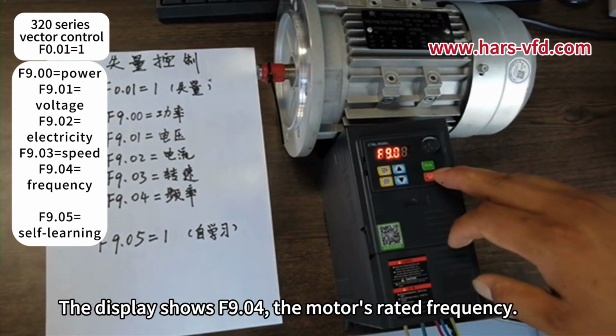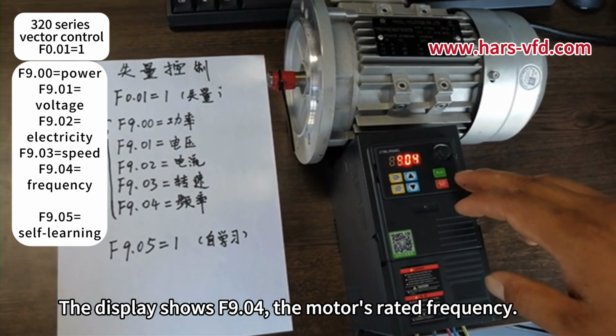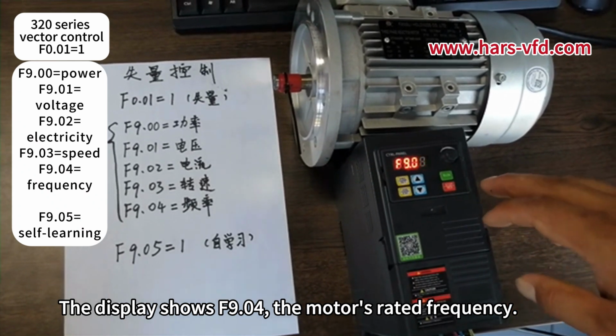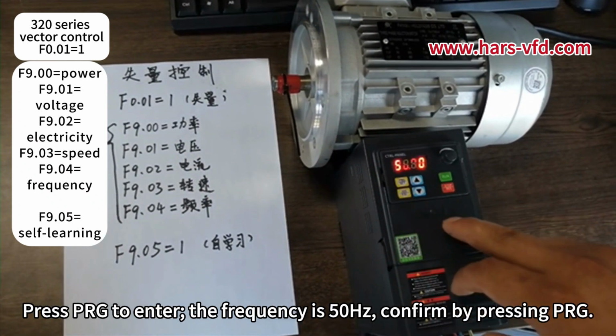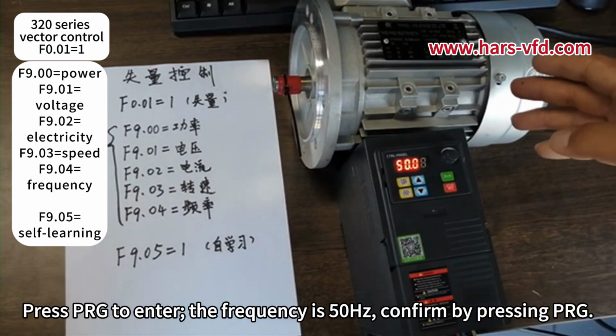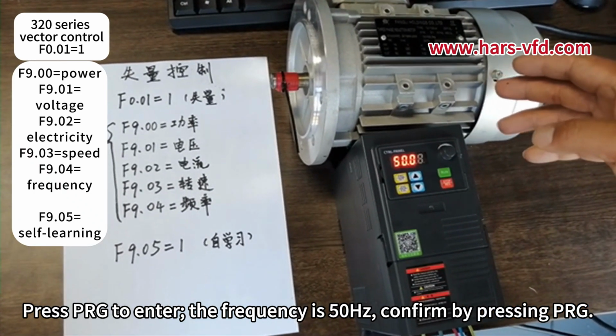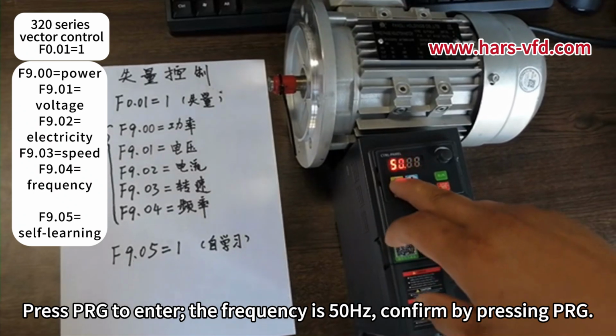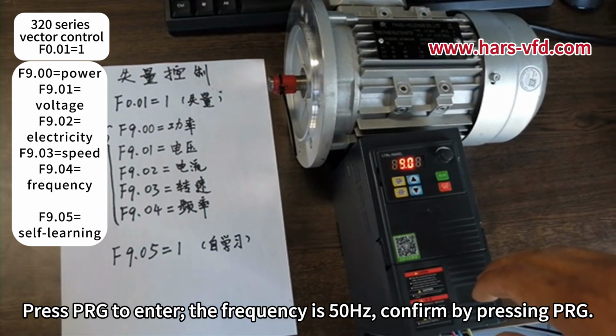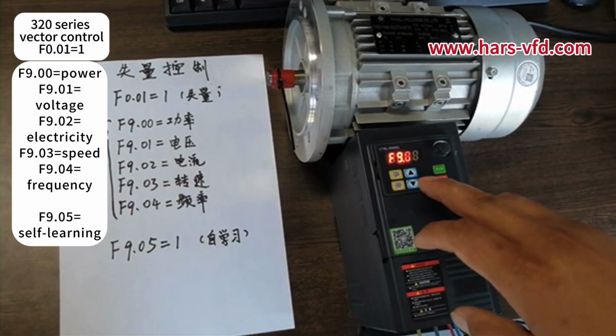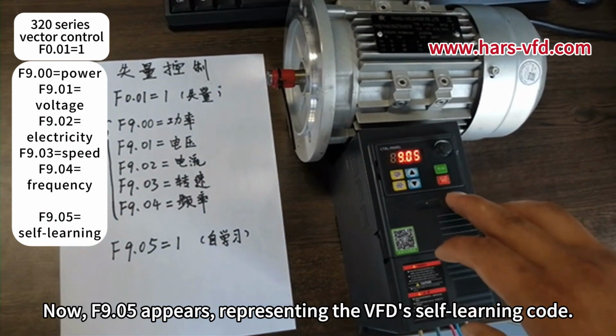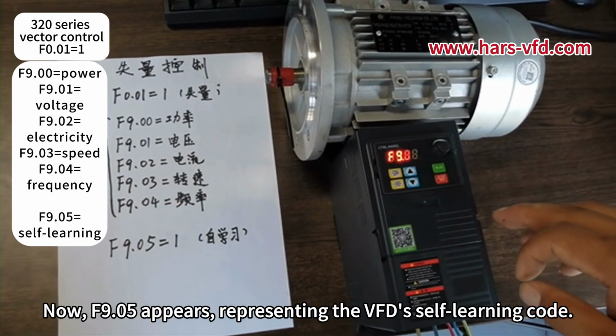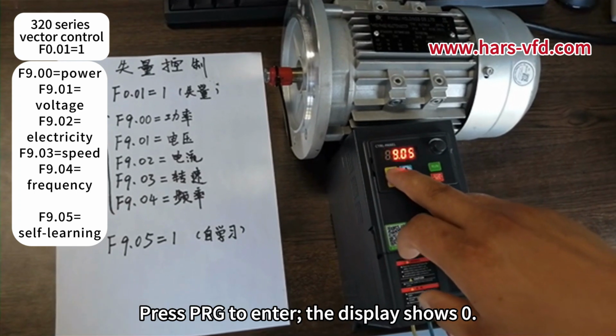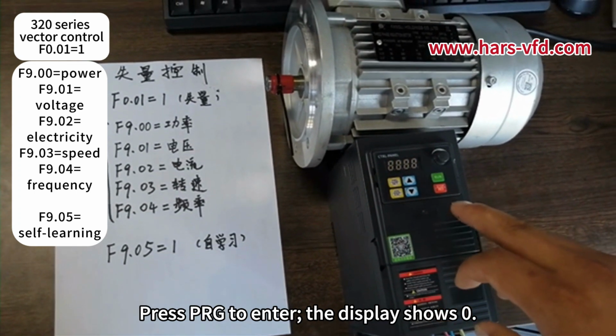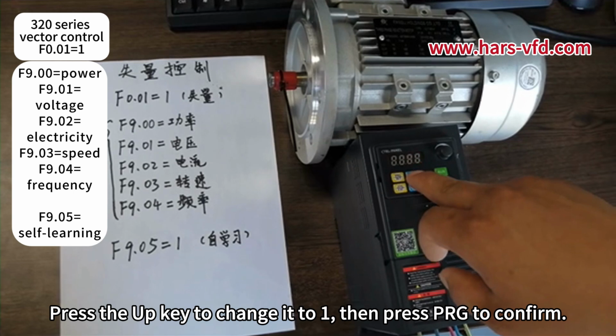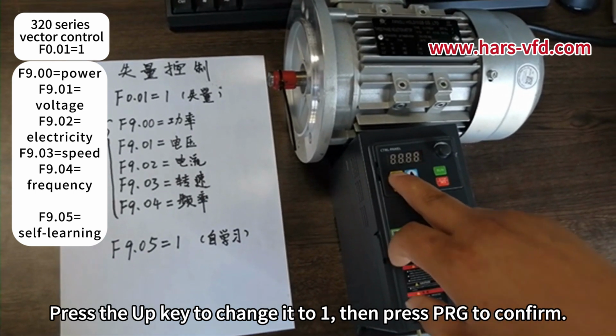The display shows F9.04, the motor's rated frequency. Press PRG to enter. The frequency is 50 Hz. Confirm by pressing PRG. Now, F9.05 appears, representing the VFD self-learning code. Press PRG to enter. The display shows 0. Press the up key to change it to 1, then press PRG to confirm.